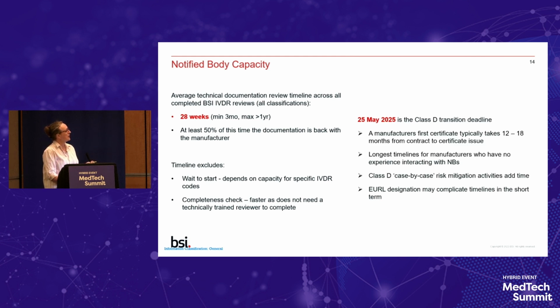So for the 25th of May 2025 Class D transition deadline, a manufacturer's first certificate typically takes 12 to 18 months from contract to certificate issue, and the longest timeline is for those manufacturers without experience interacting with notified bodies. Second certificates, or second products to go through technical review, usually go faster than the first. So I'd recommend getting your first files in with a notified body sooner, take all the learnings into your portfolio and then come with a big bang with everything else.